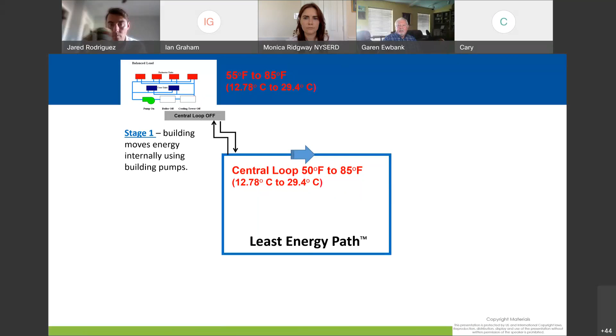However, next, when we start getting other buildings on these systems, some may be heating, some may be cooling, depending on what they're doing, we might move to what we call stage 2. So that building on the upper left, it now turns on to that central loop. If you'll look at that, that is just a big pipe, and it has a one pipe connection from the building to that central loop. Now, as long as we stay in that 50 to 85 degree range, that's all we need to do. You crank these buildings on, here it goes.